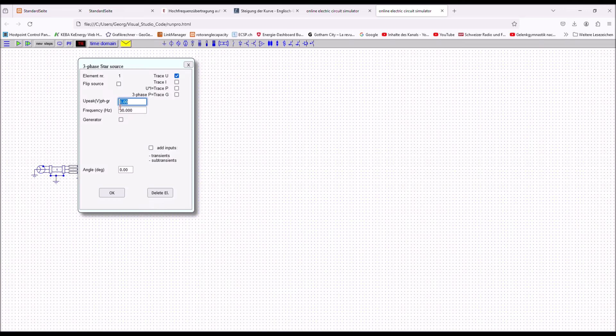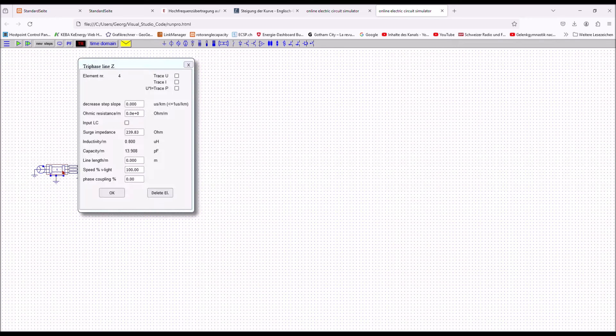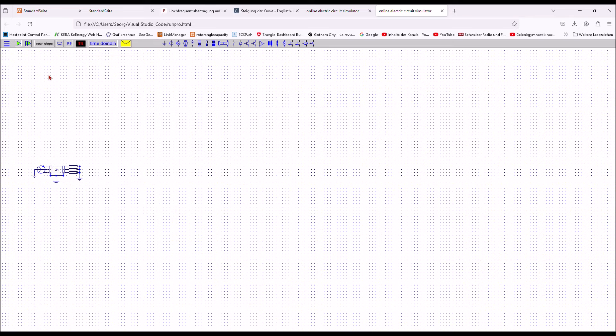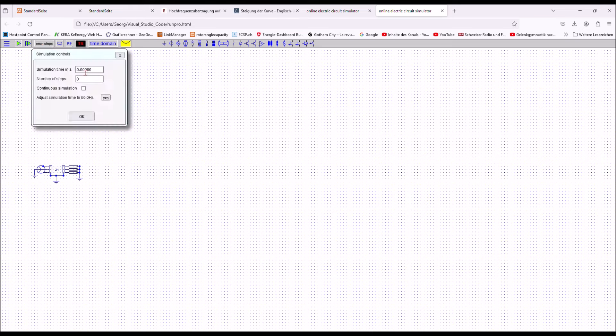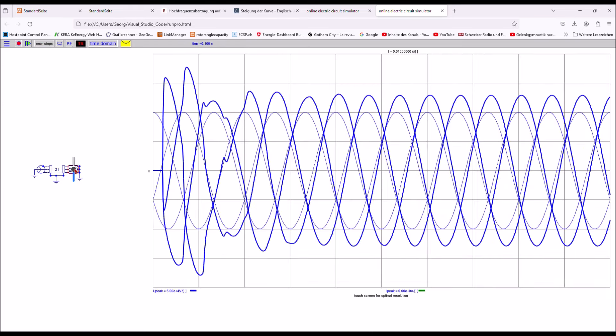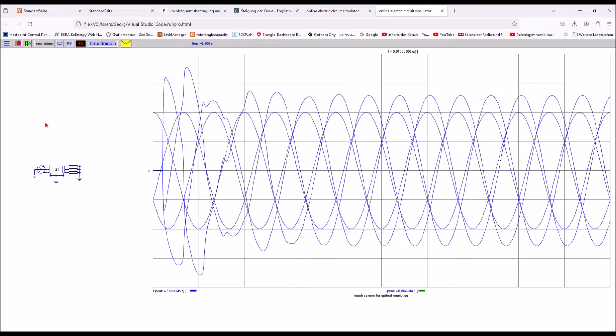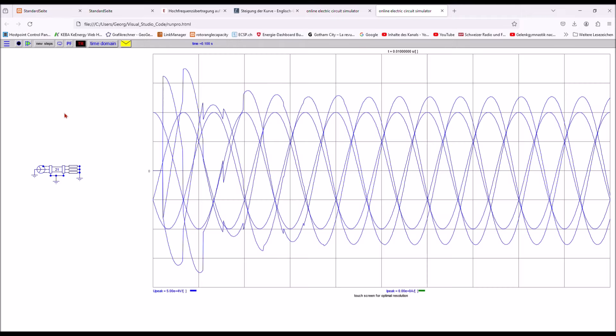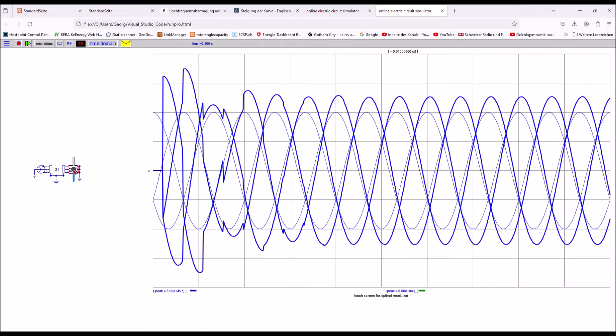In the line input form for the three phase lines, however, there is an additional input required for phase coupling. It represents the capacitive phase coupling between phases in percent of one per unit voltage. If left zero, there is no phase coupling at all. There are two simulation examples, one with 0.2 microsecond per kilometer damping and one with 0.02 microsecond per kilometer.